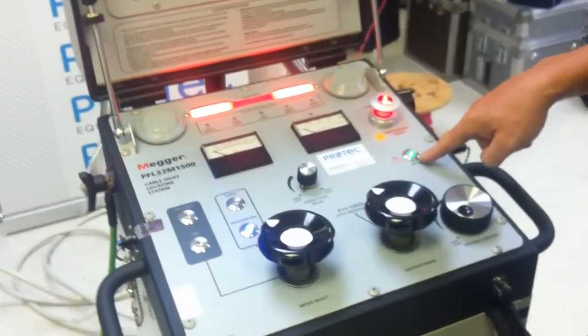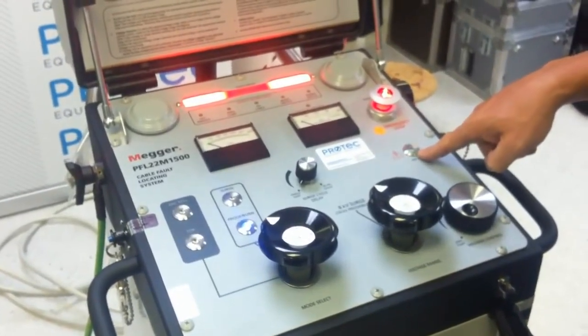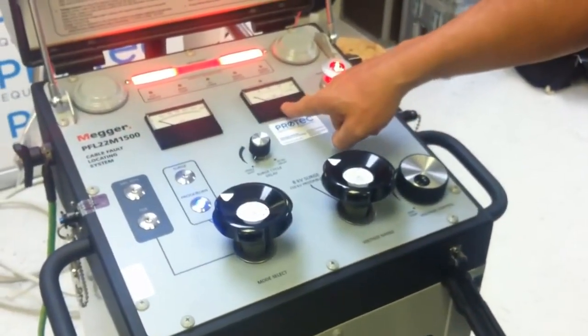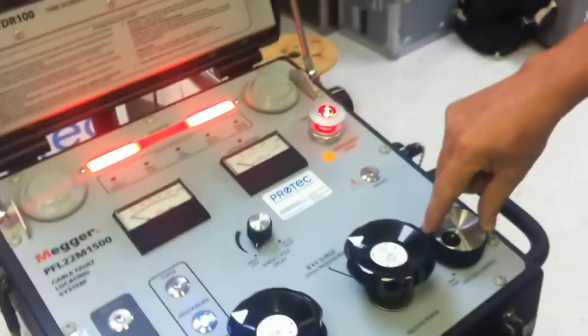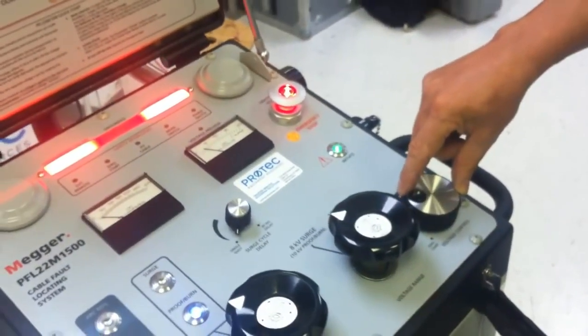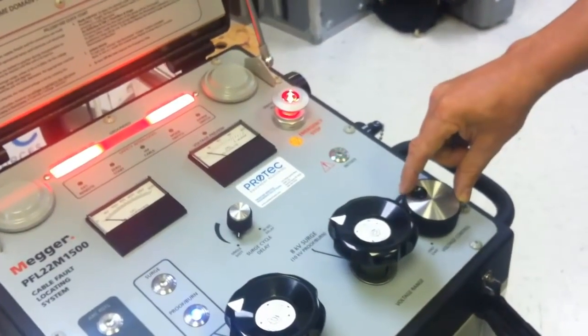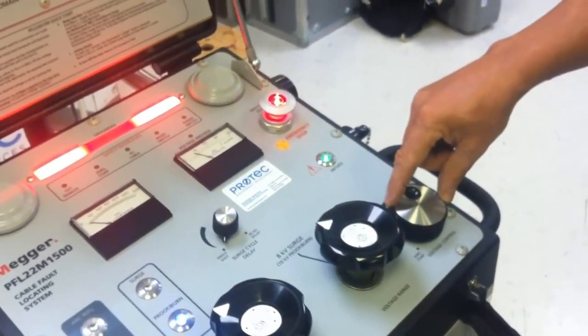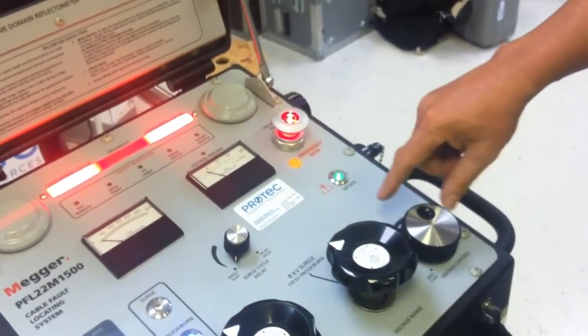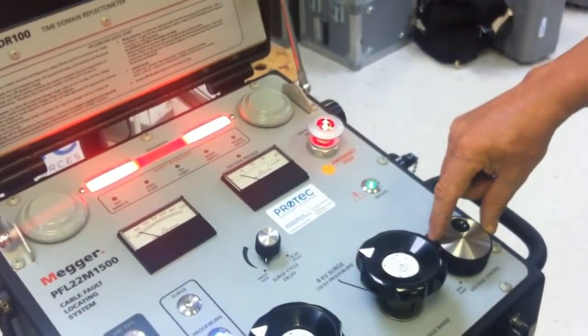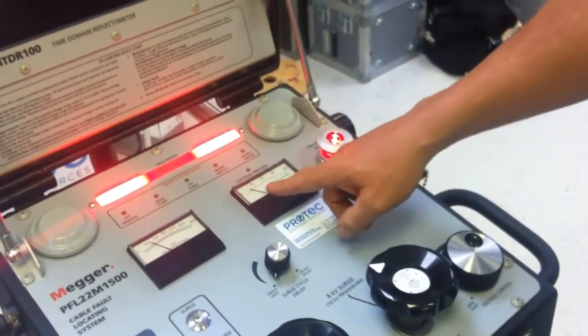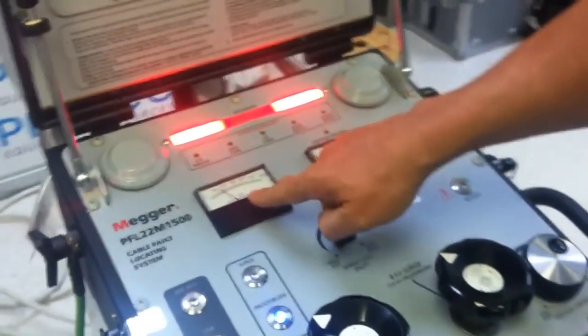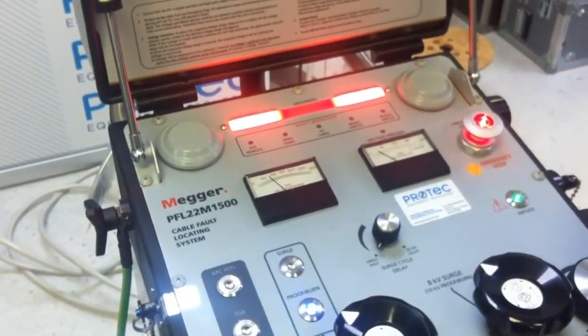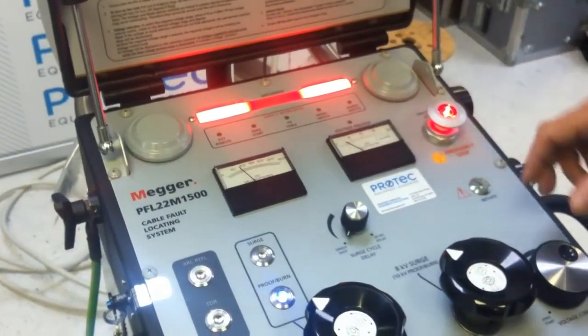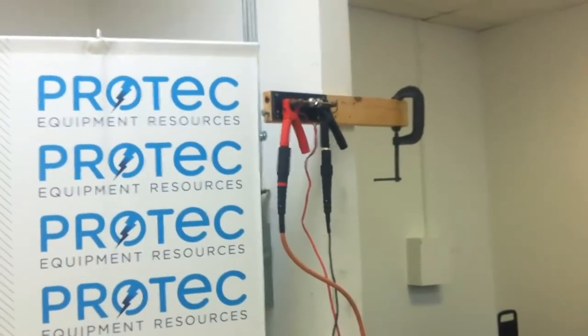The flashing green tells me now I can start performing my test. So watching my kilovolt meter, I'm going to slowly start to elevate my output voltage. Now, when I reach a point of breakdown, any further advances of my voltage control will only provide me higher fault current. So in essence, I've now left the proof mode and I'm now in a burn function. And we can see the burn down occurring at our electrodes.